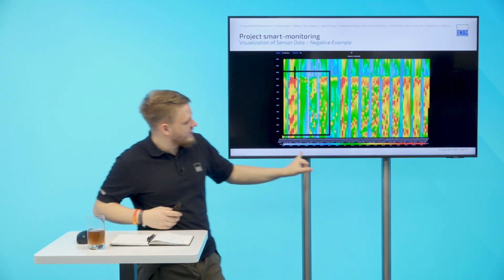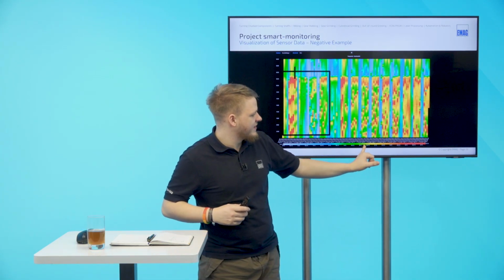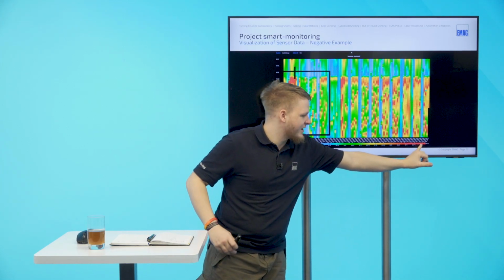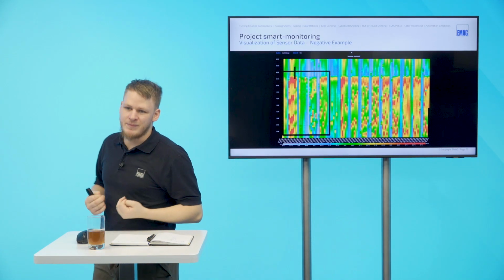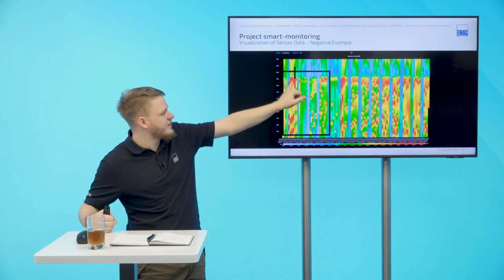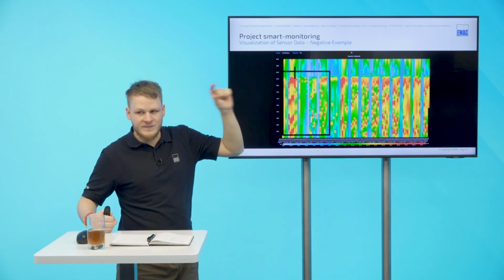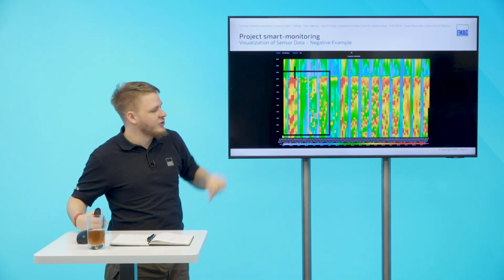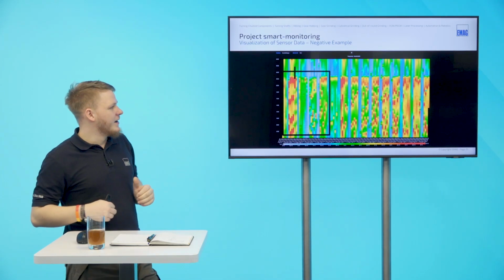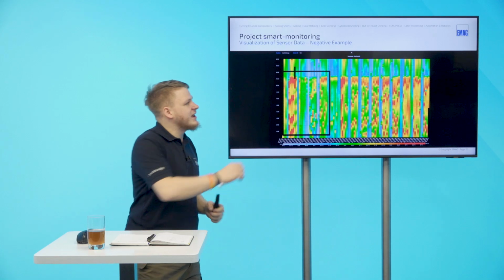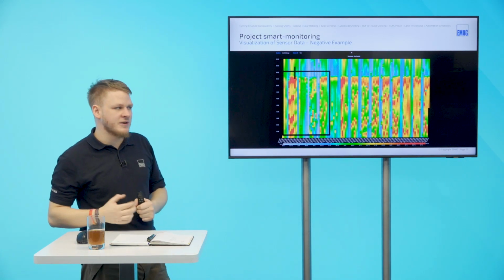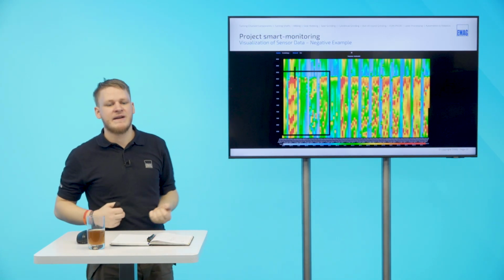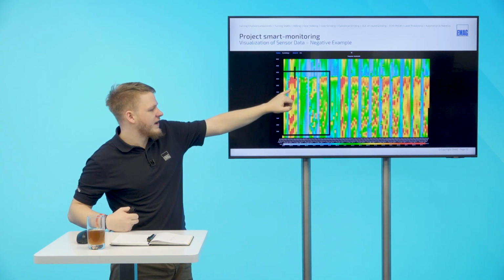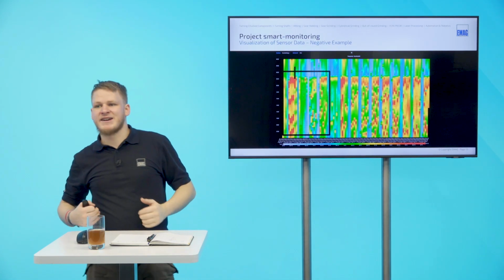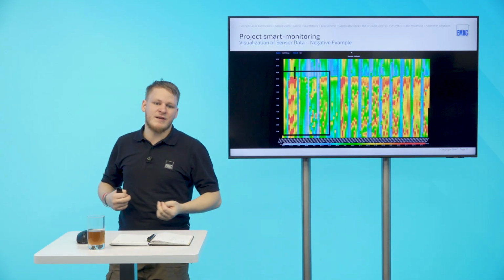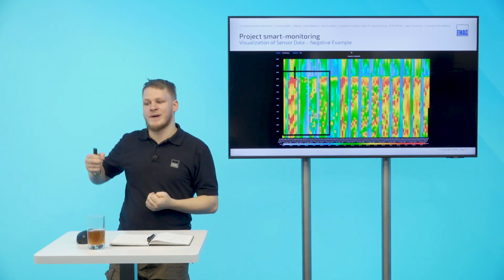Because in this color scale, we see, okay, everything above 20 degrees slowly gets yellow to orange, and at 24, we reach a dark, deep red. And if we look at the left side, the first week, we see a lot of long red periods in the 2 to 3 hour time range, which means the factory heated up to above 24 degrees and tried to keep that for several hours before it turned off again, cooled down pretty fast, and tried to heat again. And we wasted a lot of energy because the temperature was adjusted way too high.